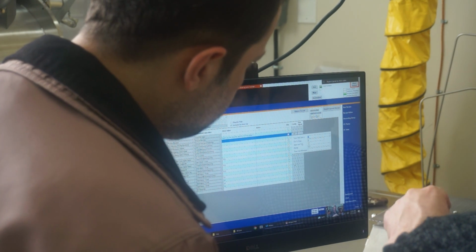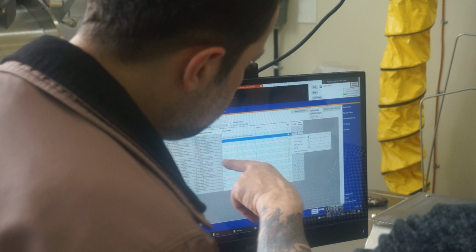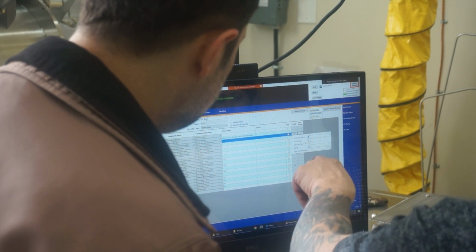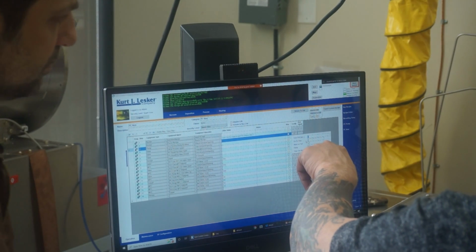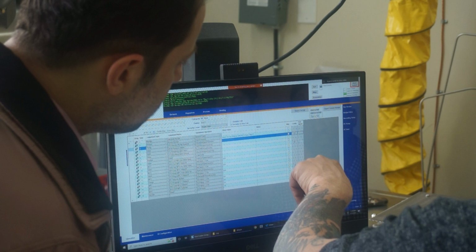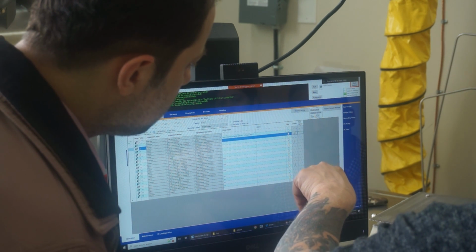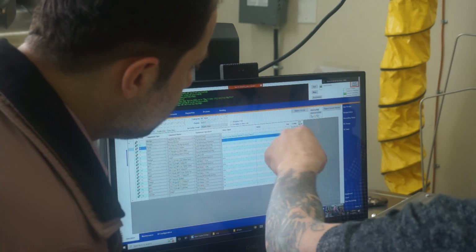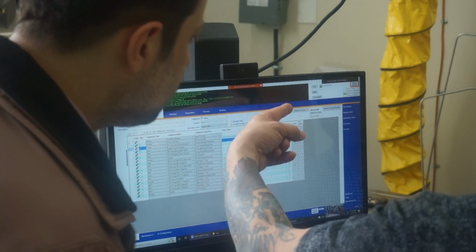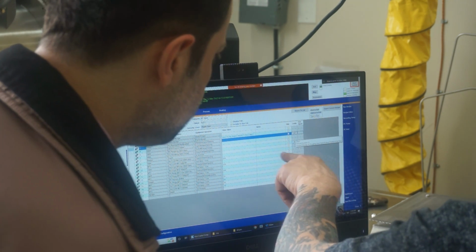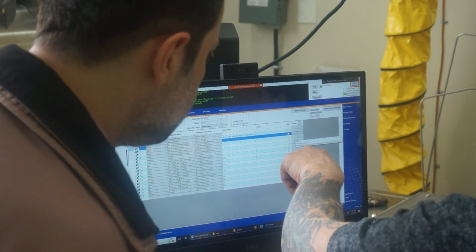So it gives it 1 second, and if this is off, it automatically goes to step 8. So the T part of it, there's time associated and it goes somewhere. Go-to steps you could have jump forward or you can have it looping. You could jump back.